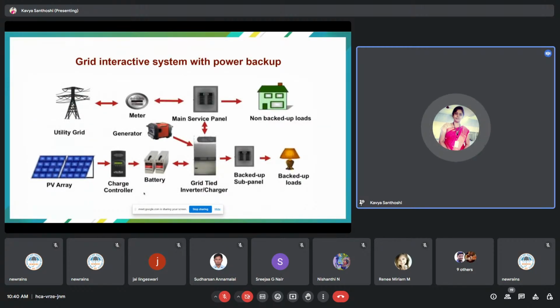In this grid interactive system, the main blocks involved with power backup, meaning with battery, include the grid. Before we connect to the grid, we have the meter and the main service panel, and we have the non-backup loads, that is load requirements like AC or other loads like fridge, which receive a certain wattage.